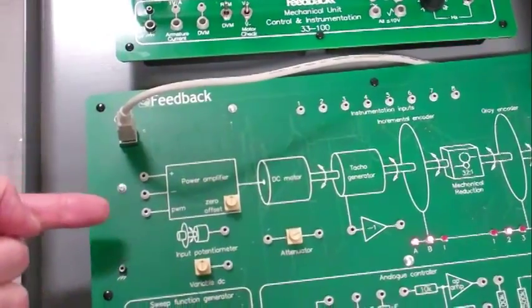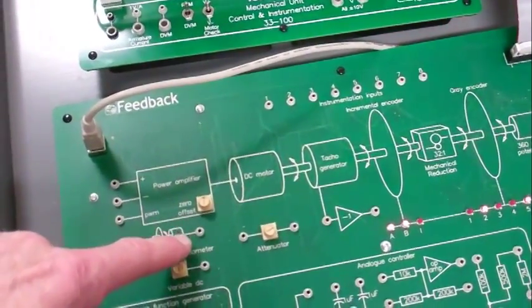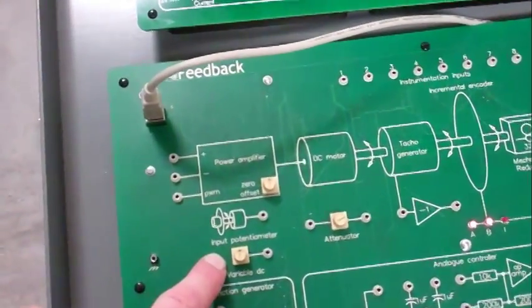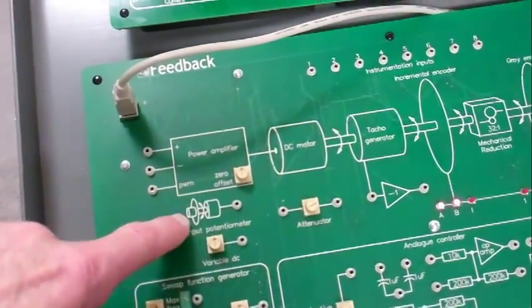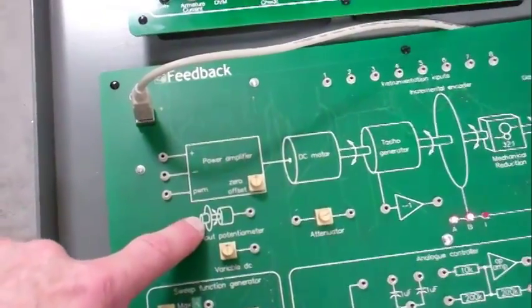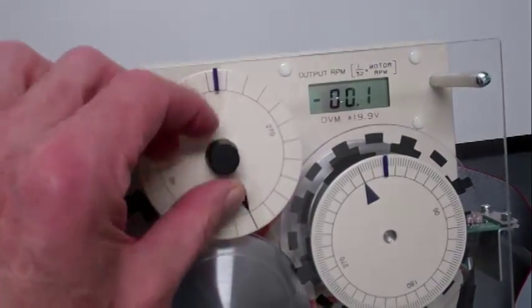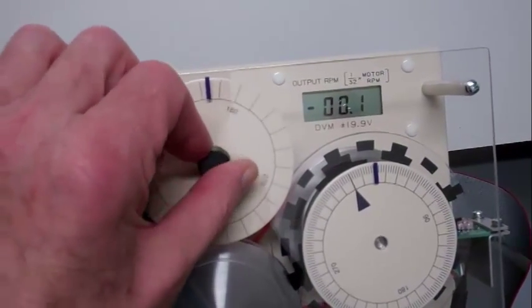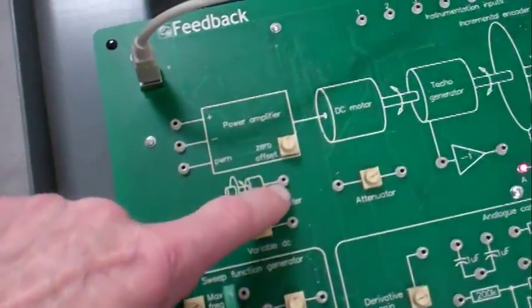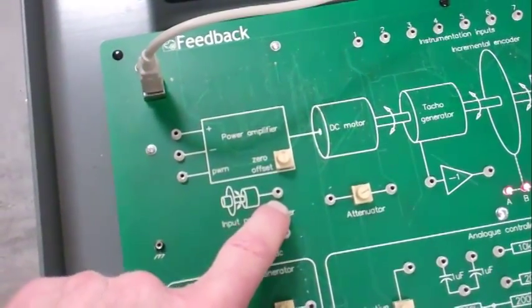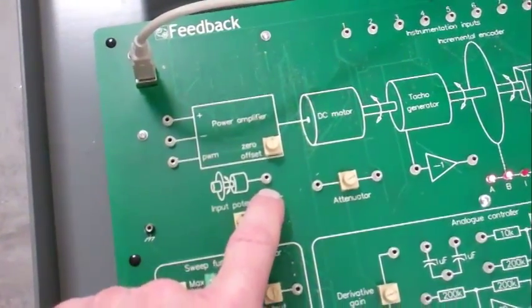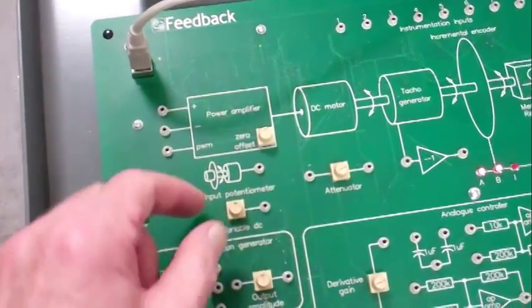That control voltage is generated several ways. One way is through the input potentiometer. The picture of the input potentiometer is shown here. The actual input potentiometer is right here. It will turn almost 180 degrees either way from zero, and that will make a plus or minus one volt signal show up there. This potentiometer will do the same thing.